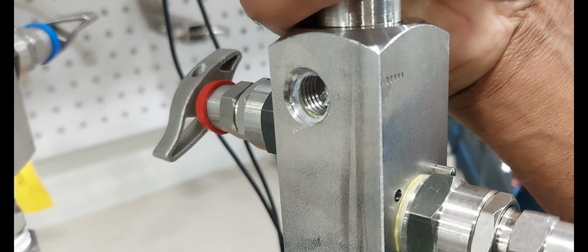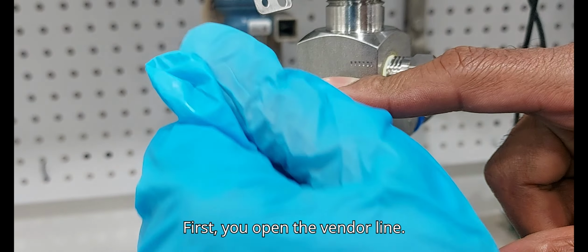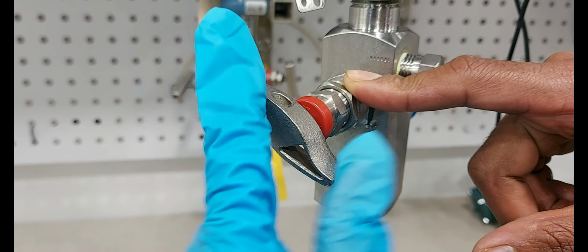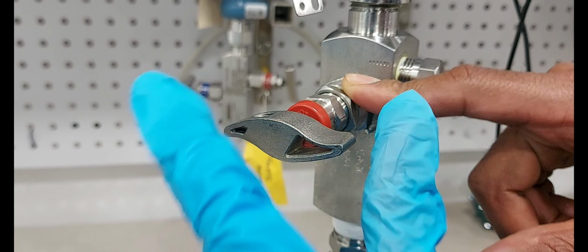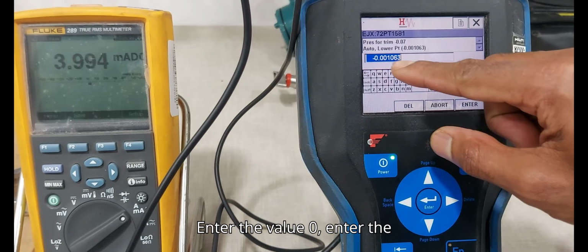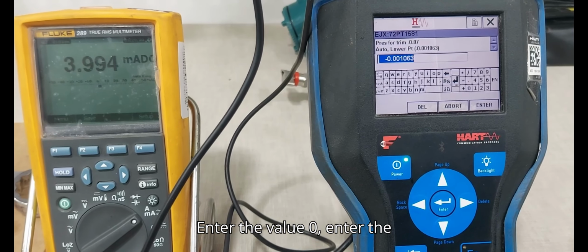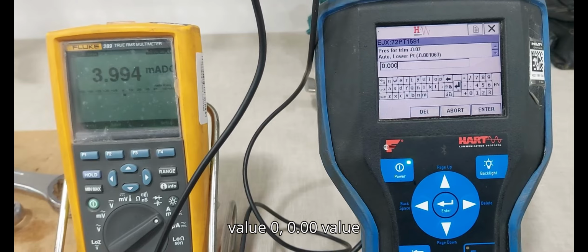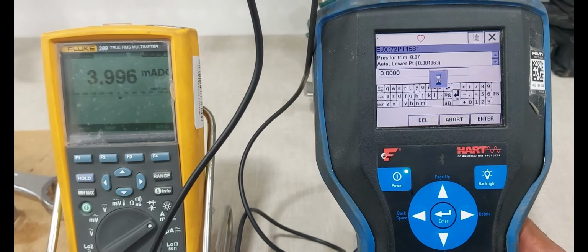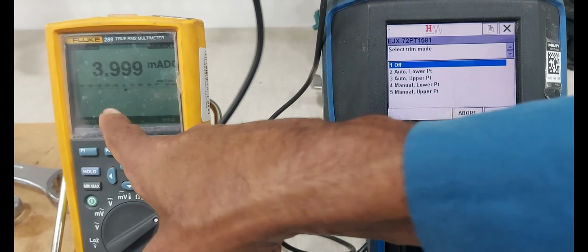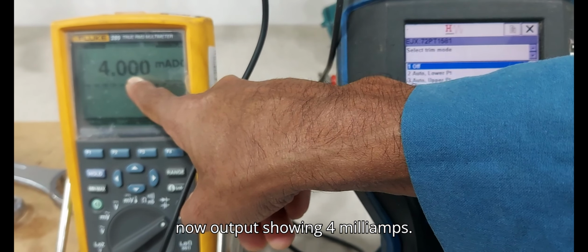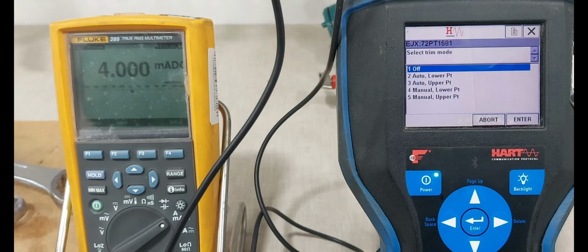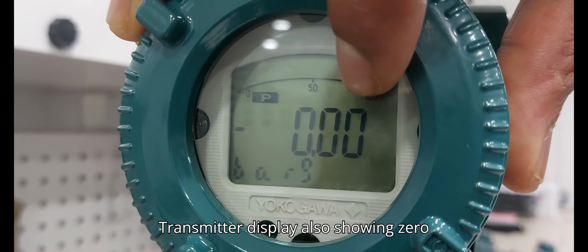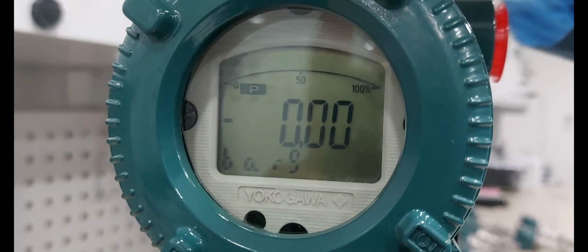Once calibrated, we will remove the vent port. First, open the vent line. Enter the value 0, 0.00. Enter. Now the output shows 4 milliamps. The transmitter display also shows 0 bar.